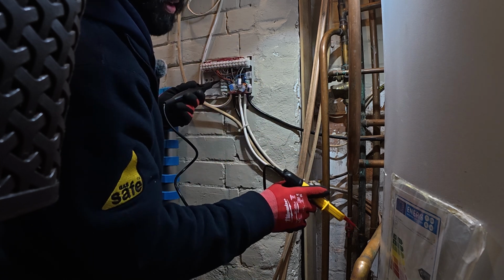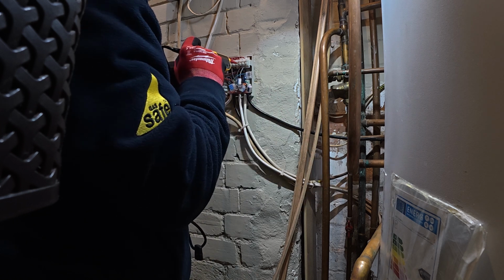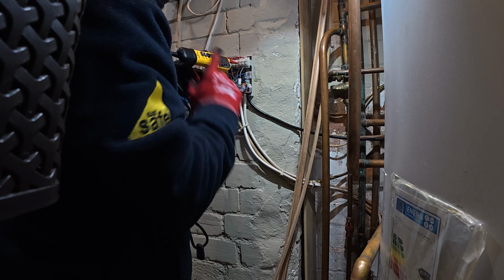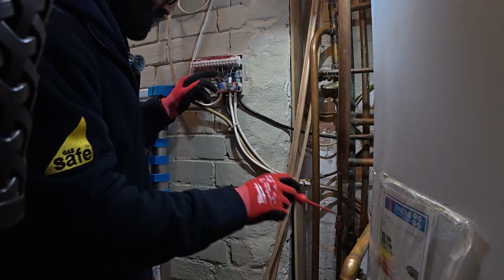The fault lies with the cylinder stat because there's power from the programmer going to the cylinder stat. So power to the cylinder stat, but nothing coming back from the cylinder stat. Faulty cylinder stat.